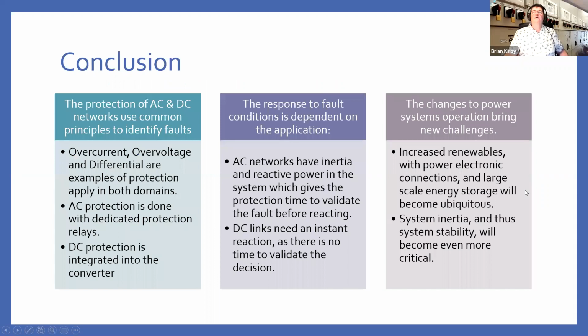Okay, I know I'm slightly over the hour, so I shall get into my conclusions here. AC and DC networks, they have common principles of protection, but they have different application domains. So overcurrent, earth fault, overvoltage, differential are protection schemes that apply in both domains. But on AC protection, you have a dedicated device, whereas on DC protection, it's integrated into the converter station.